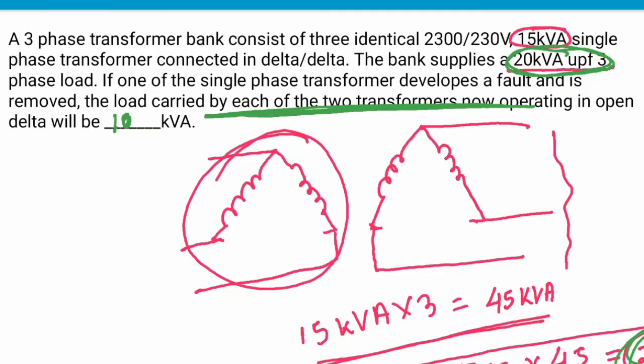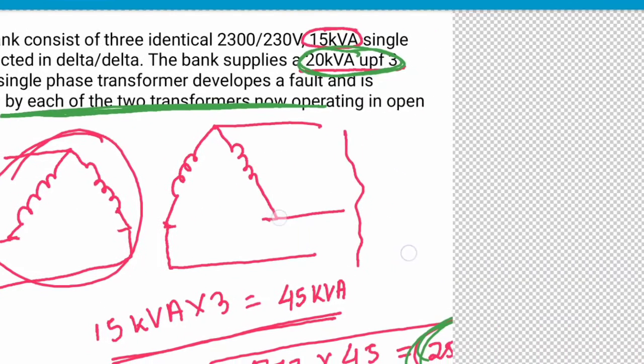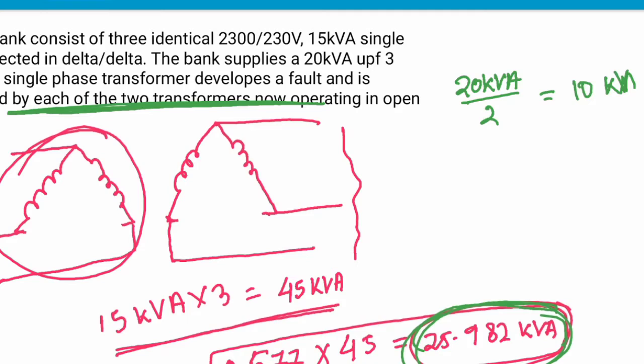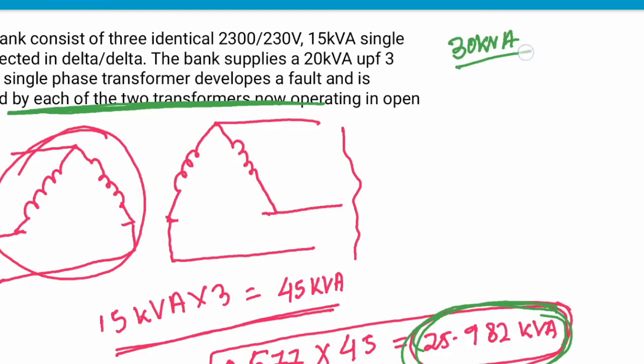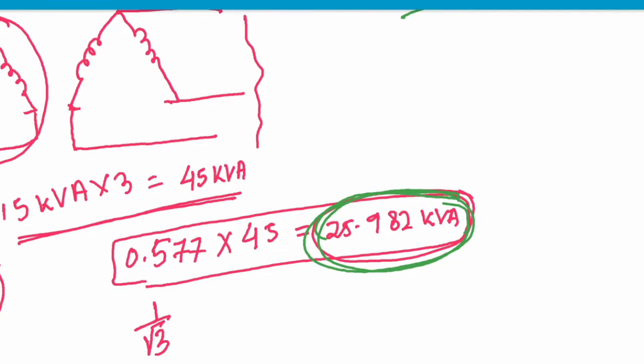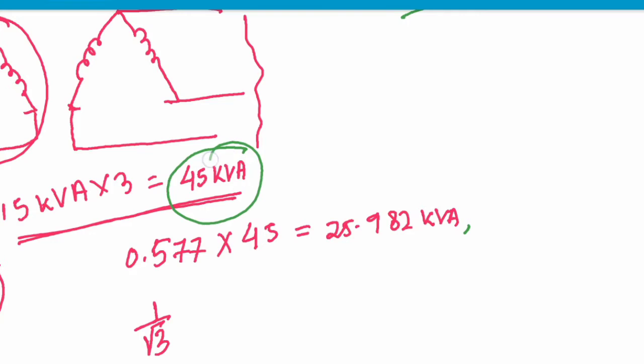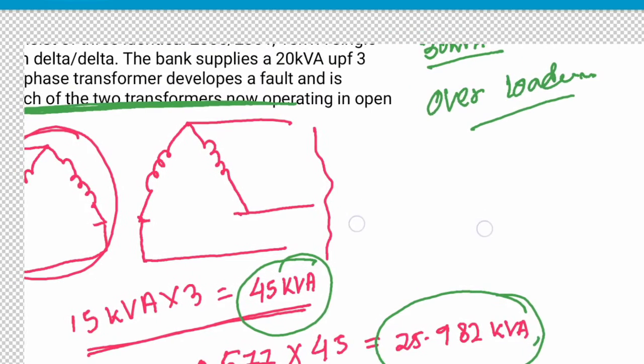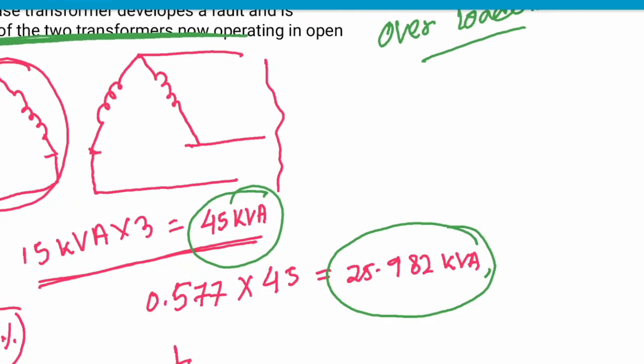But what is the difficulty in this question? There is no difficulty in this question, but if the load, instead of 20 kVA, were given as 30 kVA, then when the system is converted to open delta or VV connection, it would provide 30 kVA but in an overloaded condition, and it will not work for a long time because the efficiency has decreased and the rating has decreased from 45 kVA to 25.98 kVA. So here the given load is less than that decreased rating.